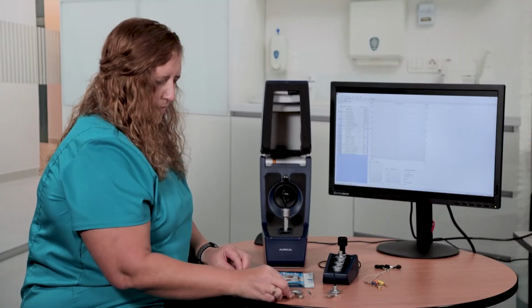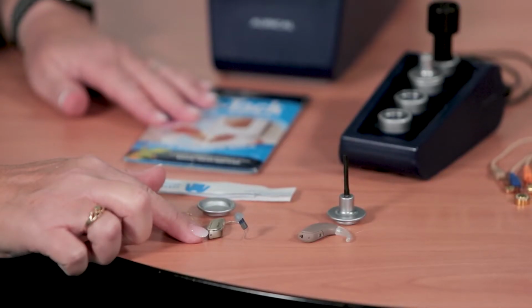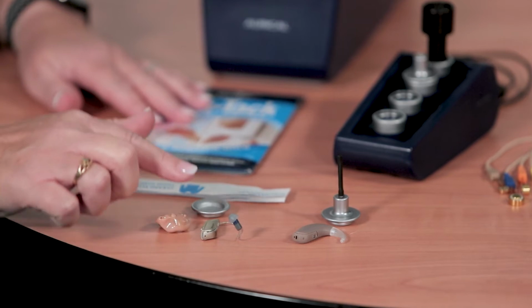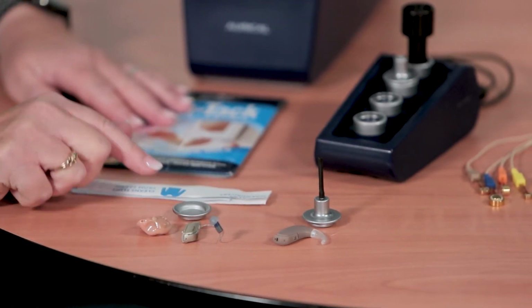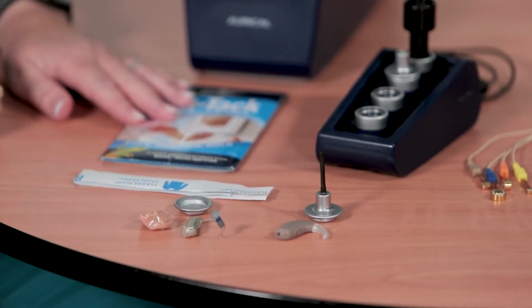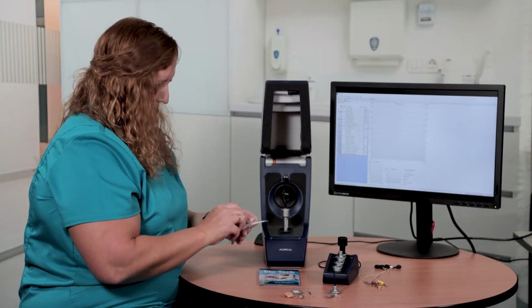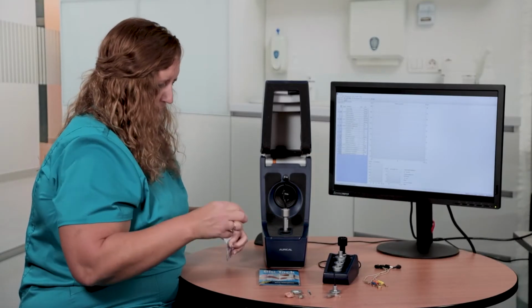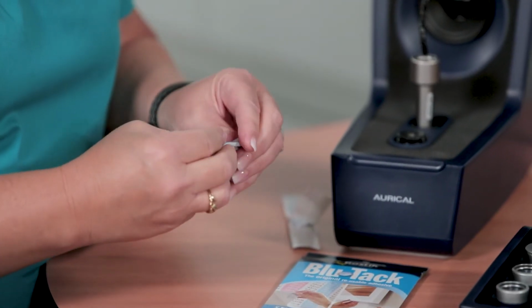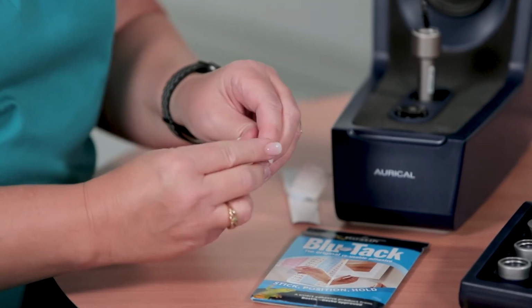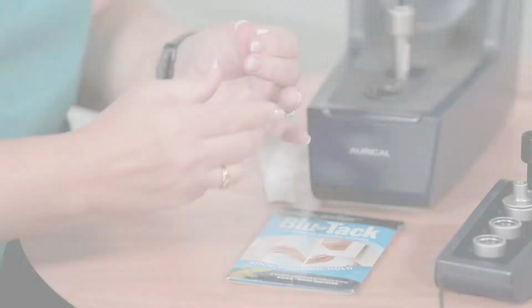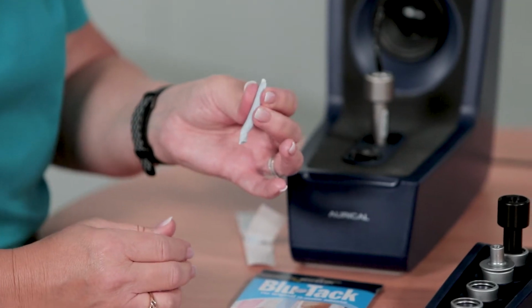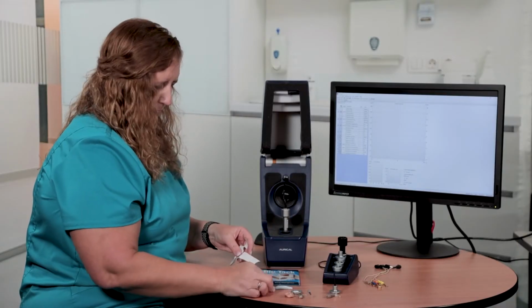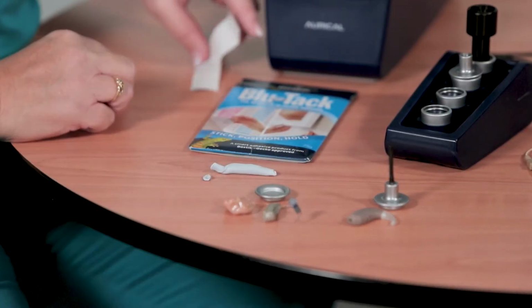For thin-tube hearing aids, receiver-in-canal devices, and custom in-ear hearing aids, the HA1 adapter and a small amount of acoustic putty is required. Begin by rolling out the acoustic putty into a tube shape, roughly 5 mm in diameter and 100 mm long, reserving a second, much smaller piece for later.